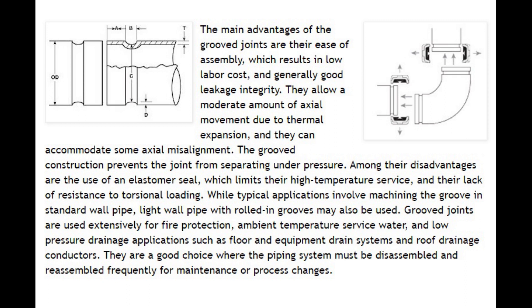Among their disadvantages are the use of an elastomer seal, which limits their high temperature service, and their lack of resistance to torsional loading. While typical applications involve machining the groove in standard wall pipe, light wall pipe with rolled-in grooves may also be used. Grooved joints are used extensively for fire protection, ambient temperature service water, and low pressure drainage applications such as floor and equipment drain systems and roof drainage conductors. They are a good choice where the piping system must be disassembled and reassembled frequently for maintenance or process changes.